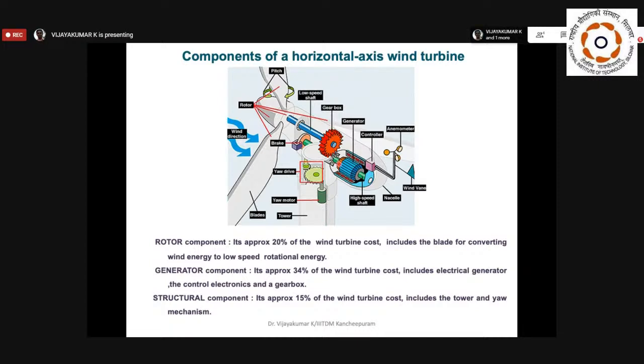This low speed shaft is connected to the generator through a gearbox. Why do we need a gearbox here? Consider our 50 hertz power supply system. For a 50 hertz supply, considering 4 poles in the generator, the synchronous speed of the generator is 1500 RPM. So for generating power, you have to rotate this generator at 1500 RPM. But in the low speed shaft, what's my speed? It's 50 RPM. So you have to match this 50 RPM with the 1500 RPM generator speed, and for that we need to use the gearbox. The gearbox cost is higher in wind turbines, so nowadays people are working on gearless wind turbines.